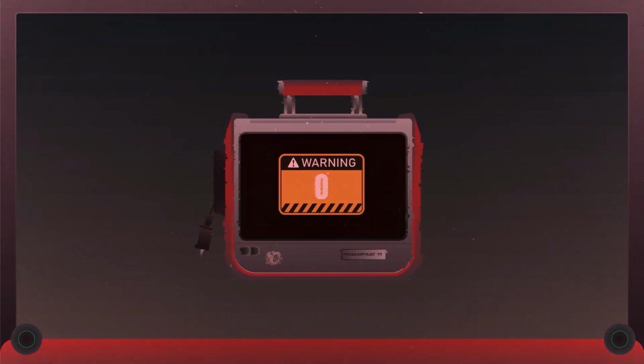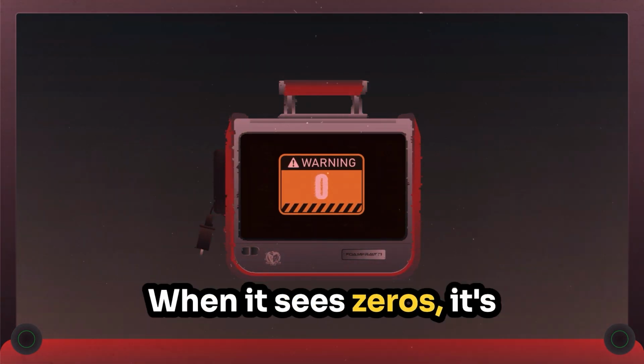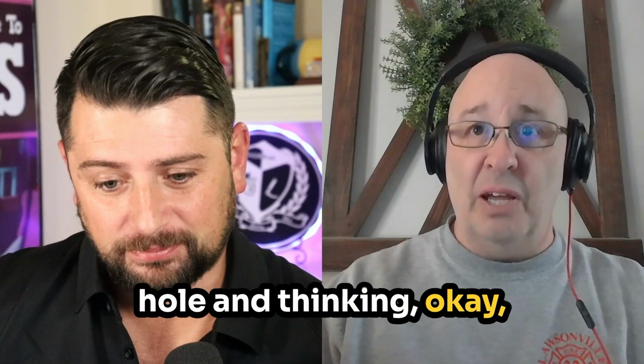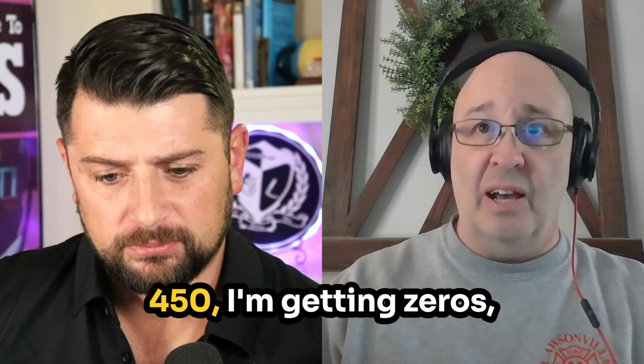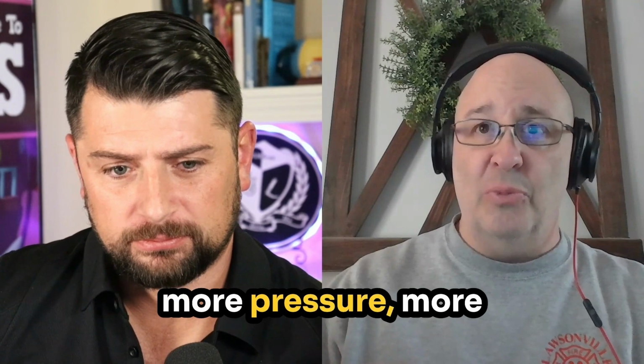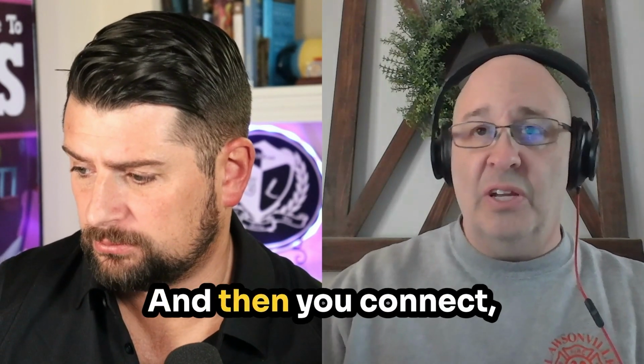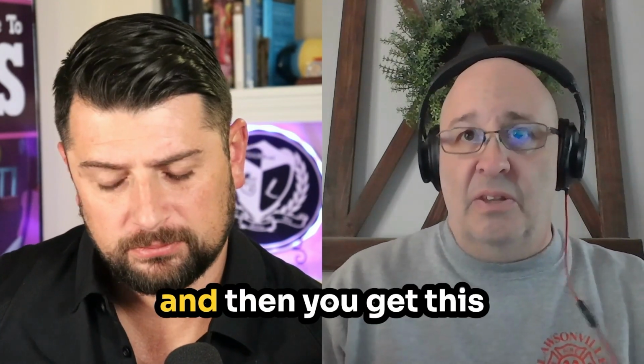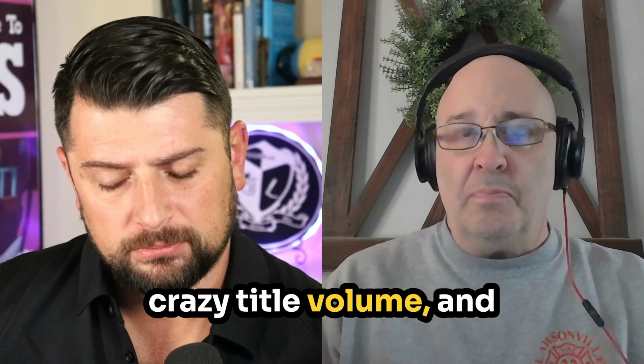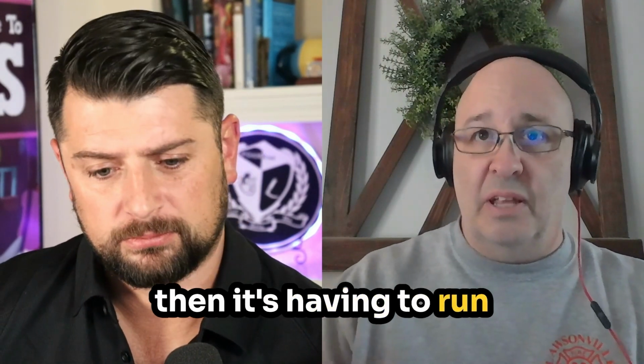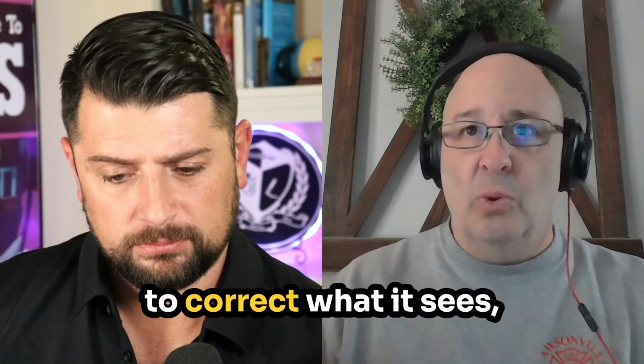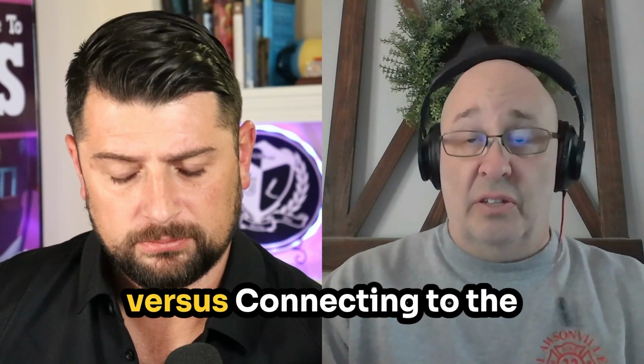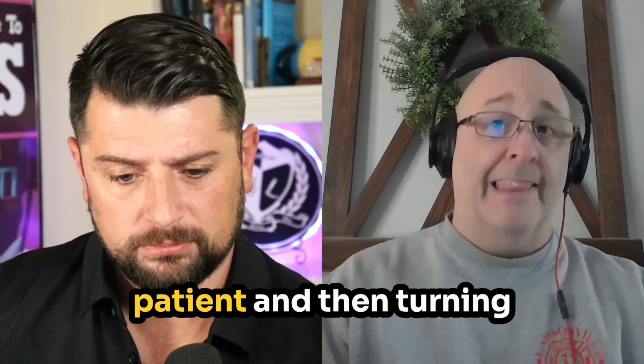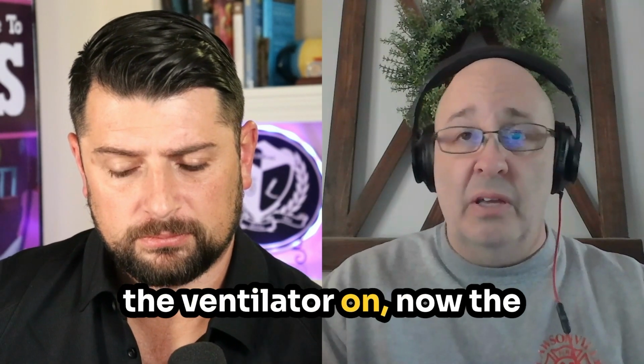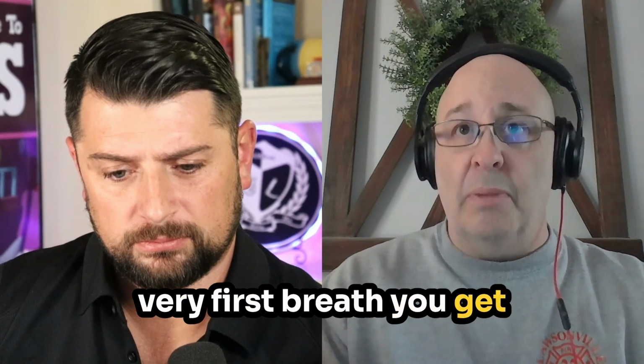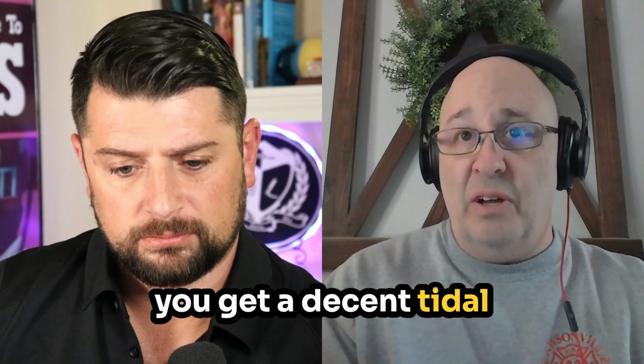Yeah. So when it sees zeros, it's running down the rabbit hole and thinking, okay, I'm supposed to give 450. I'm getting zeros, more pressure, more pressure, more pressure. And then you connect and then you get this crazy tidal volume. And then it's having to run down this algorithm to correct what it sees, versus connecting to the patient and then turning the ventilator on. Now, the very first breath, you get meaningful data back. You get a decent tidal volume.